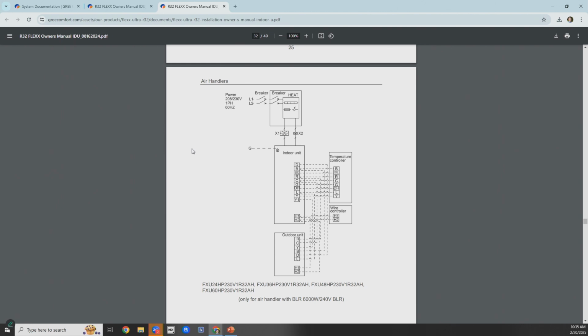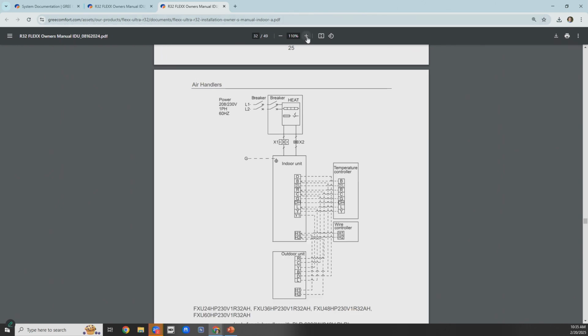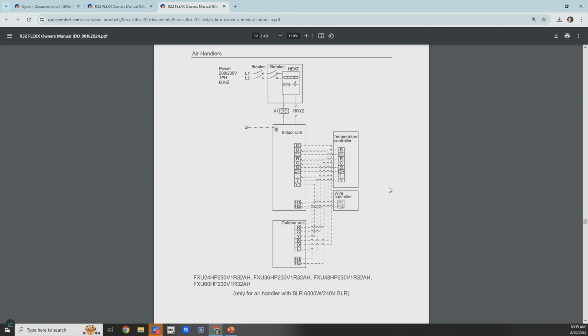but I want to readdress the whole thing with R32 and it being an A2L refrigerant, and the manufacturers are required to have an alarm that will shut the unit down if a leak is detected. And we will cover this in the video later on, what happens after it goes into alarm.